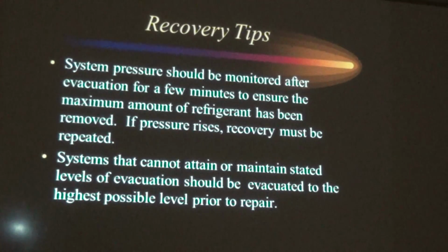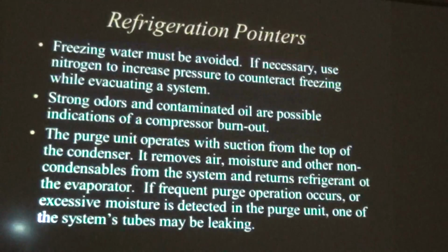System pressure should be monitored after evacuation for a few minutes to ensure the maximum amount of refrigerant has been removed. If the pressure goes up, you have to continue the recovery. That's pretty straightforward. It means there's still refrigerant there. Systems that cannot attain or maintain the level of evacuation should be evacuated to the highest possible level before the repair. Freezing water should be avoided. If necessary, use dry nitrogen to increase pressure to counteract freezing while vacuuming the system.